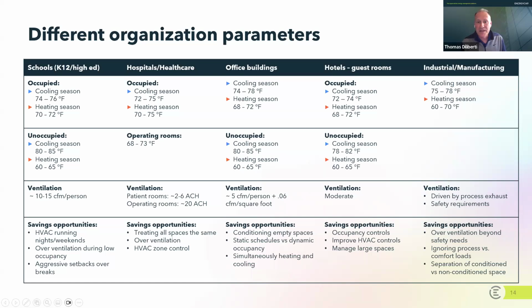I'd encourage you, if your buildings go through periods of occupancy and lack of occupancy, this is usually a great savings opportunity for most organizations during unoccupied time. During the heating season, I'm suggesting 60 to 65 degrees, but you can push the limits on this. This is often a great place to be even more aggressive if your organization can accommodate that.